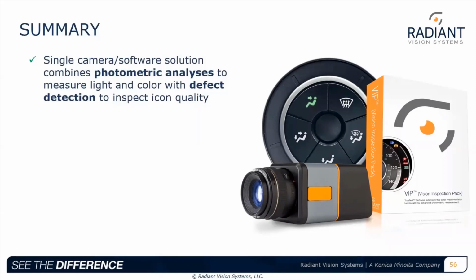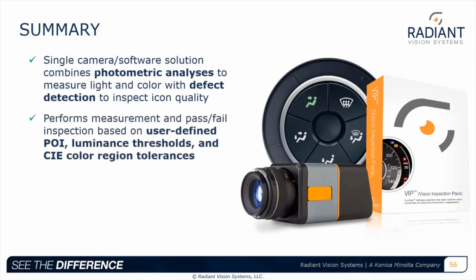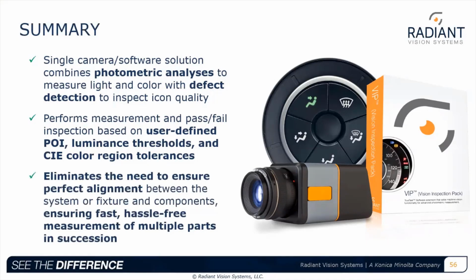So to summarize, what Radiant Vision Systems is offering is a single camera software solution that combines photometric analysis to measure light and color with defect detection to inspect icon quality. The software will perform measurements and pass and fail inspection based on user-defined points of interest, luminance thresholds, and CIE color region tolerances. And our solution eliminates the need to ensure perfect alignment between the system or fixture and components, ensuring fast, hassle-free measurement of multiple parts in succession.